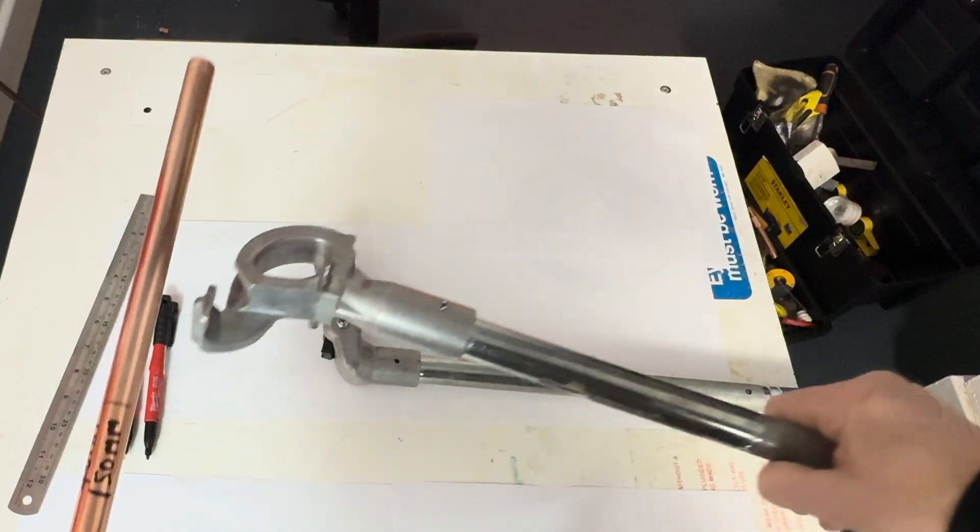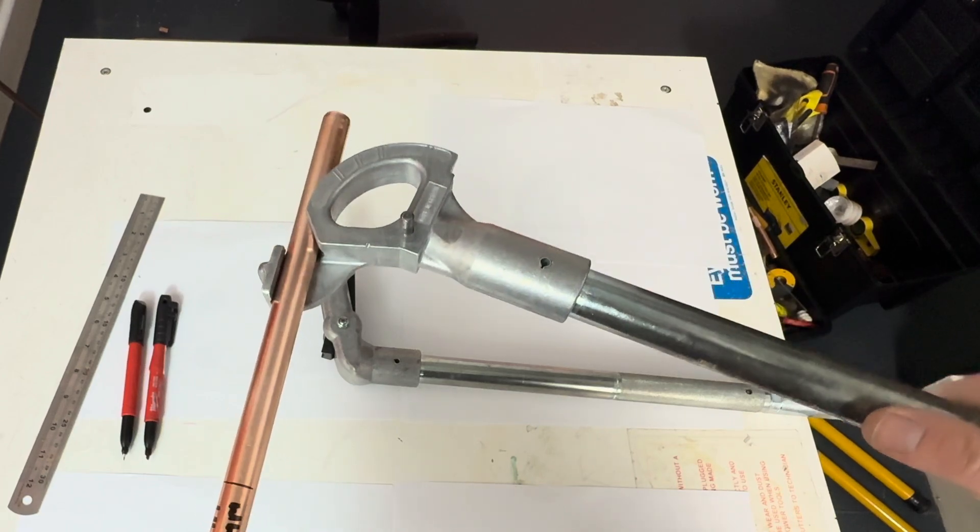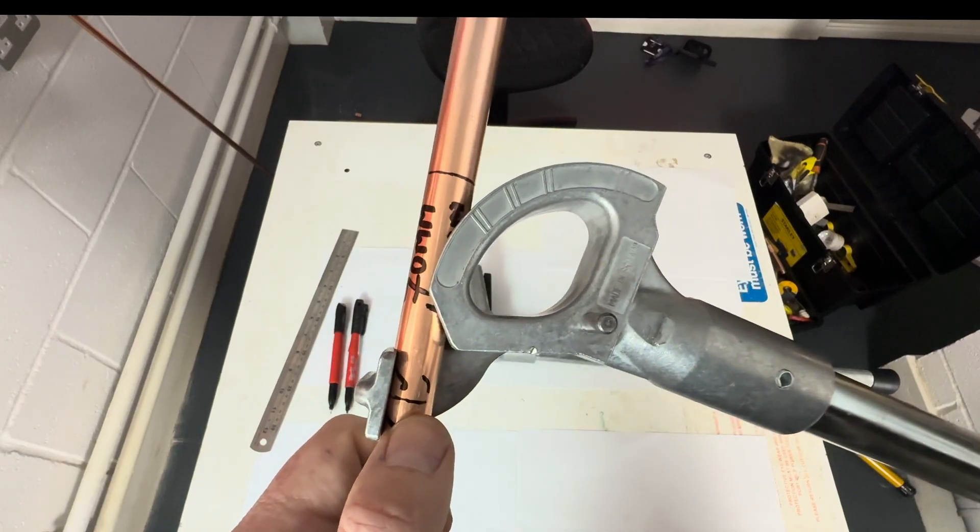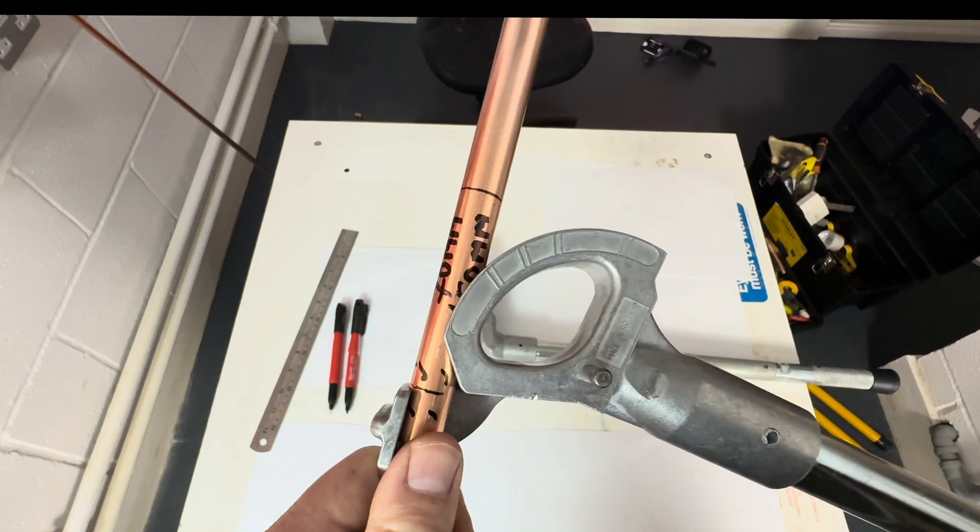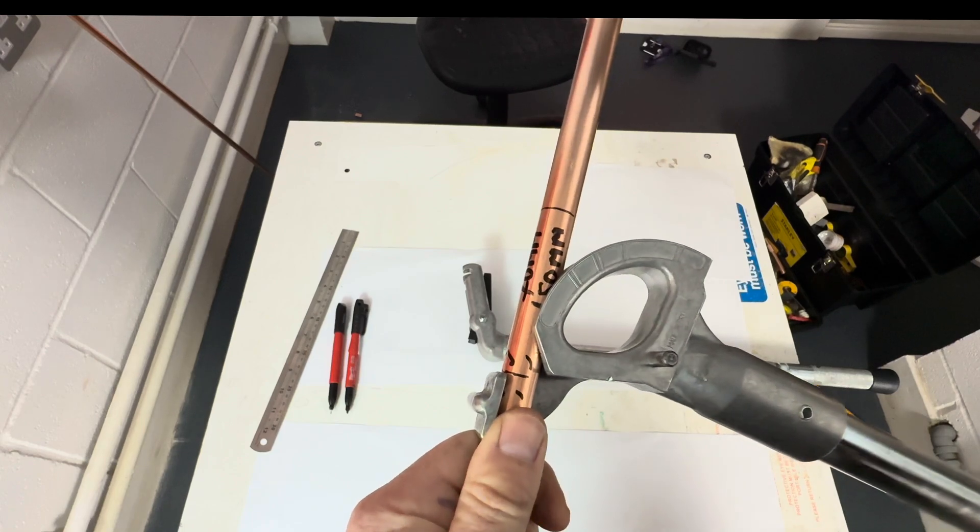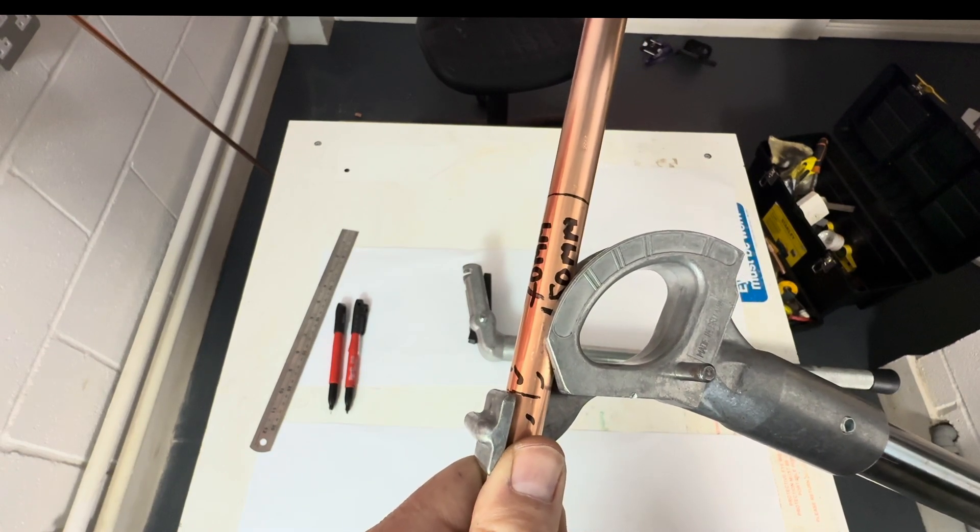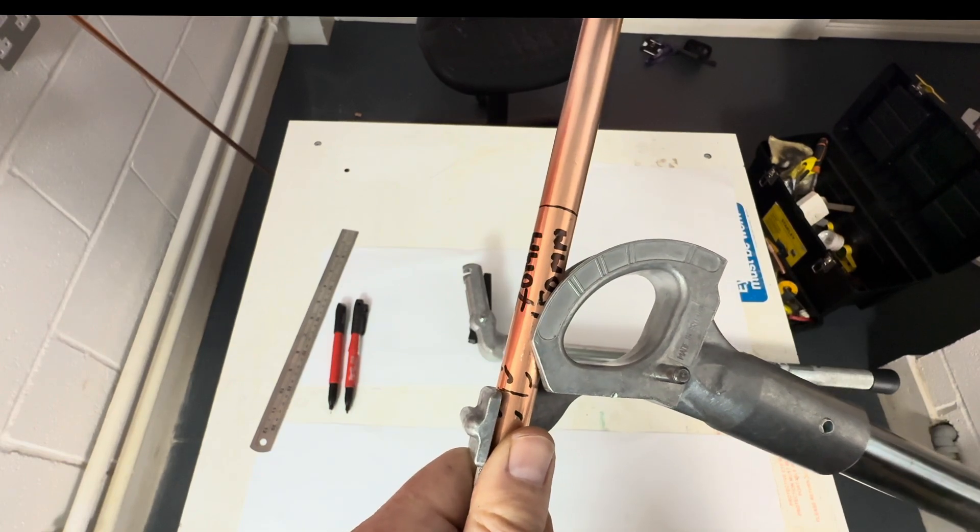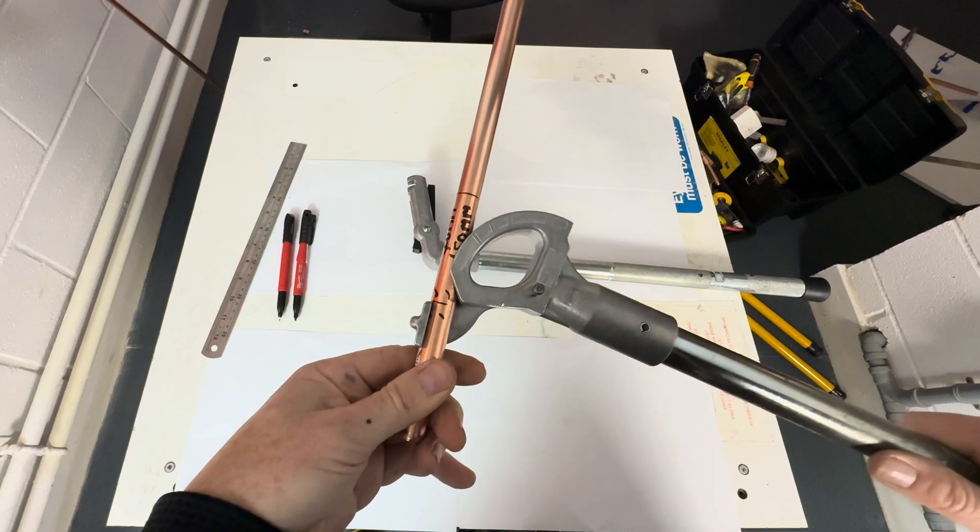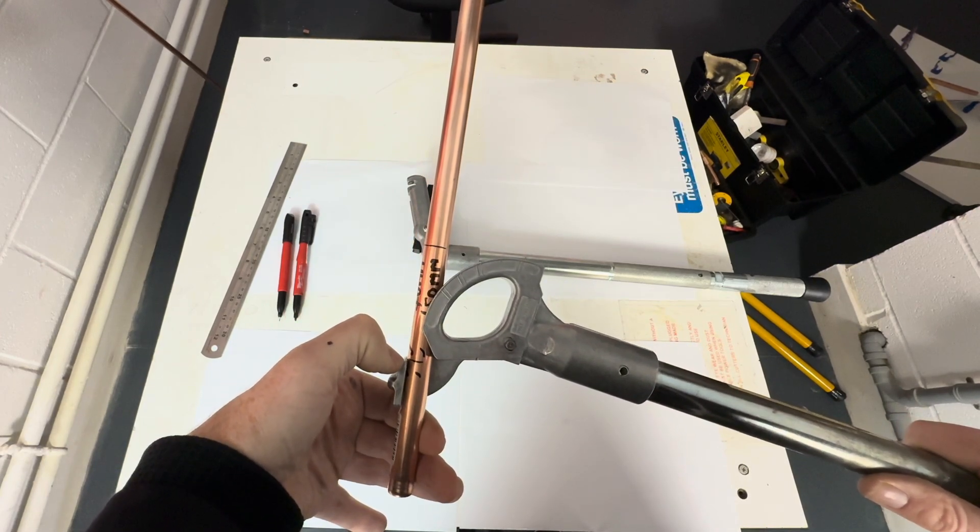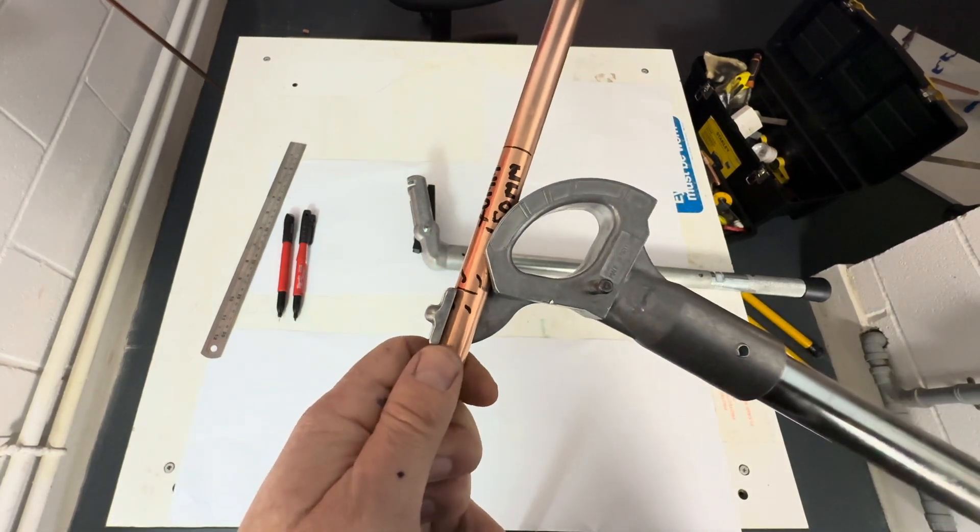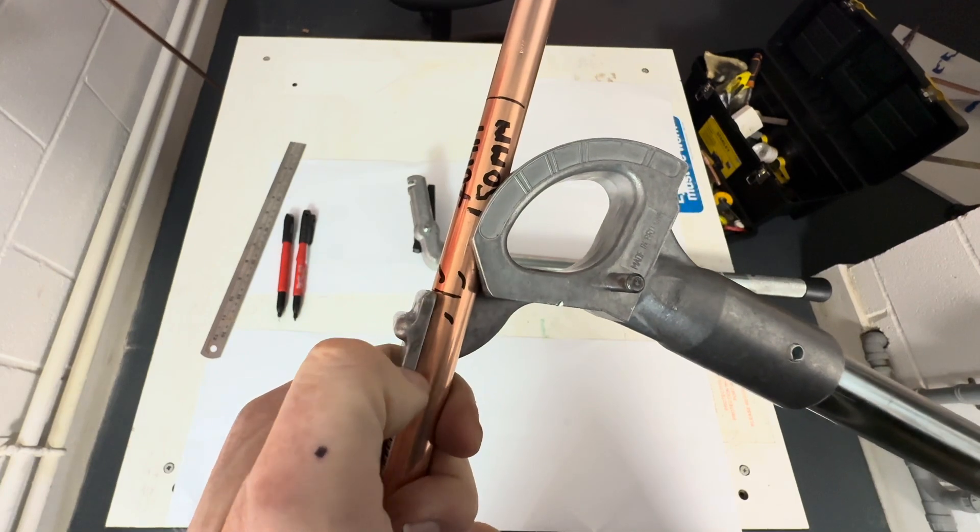Right, so we would then put our pipe into the pipe benders, and the measure back line just needs to touch the end of the stop, which is here, right there. So, that's the 150mm line. We measure back 70mm, and the 70mm line goes there.